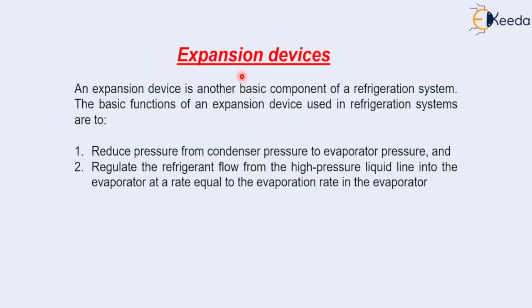Expansion devices are another basic component of a refrigeration system, just like the evaporator, condenser, and compressor. The basic functions of an expansion device used in a refrigeration system are: first, to reduce pressure from condenser pressure to evaporator pressure; and second, to regulate the refrigerant flow from the high pressure liquid line into the evaporator.